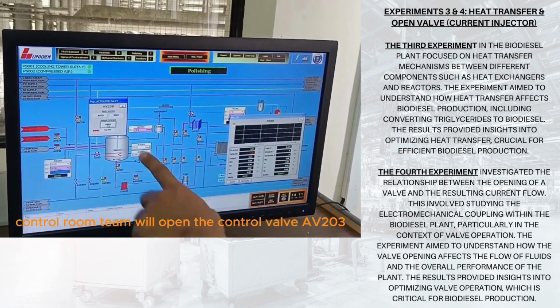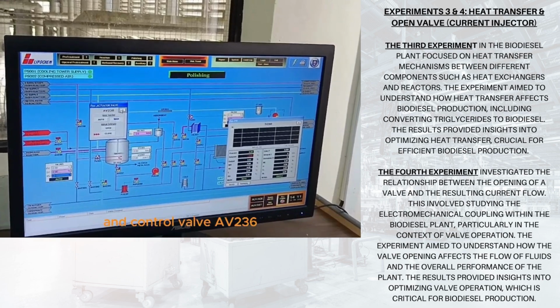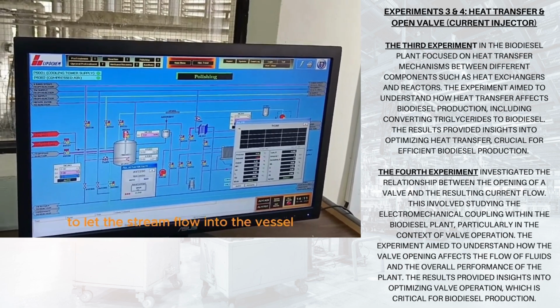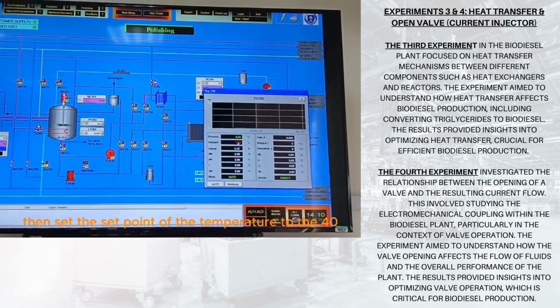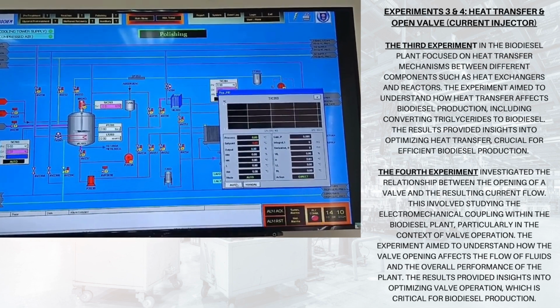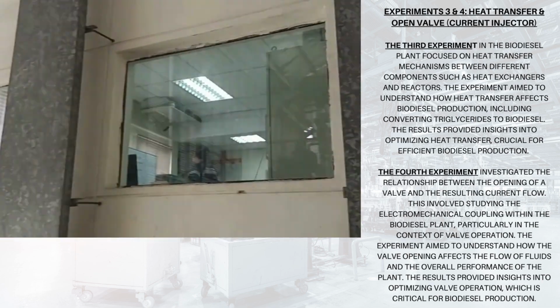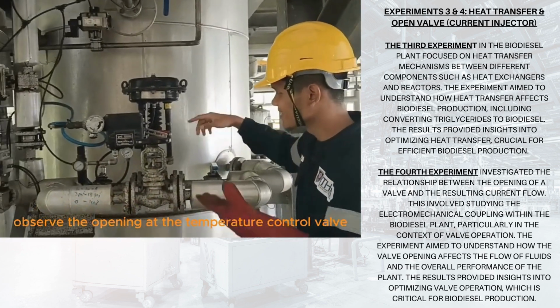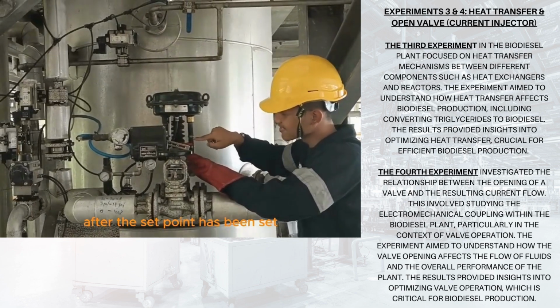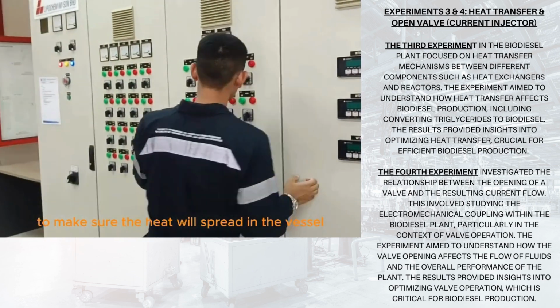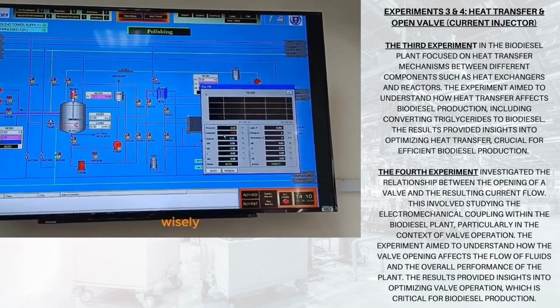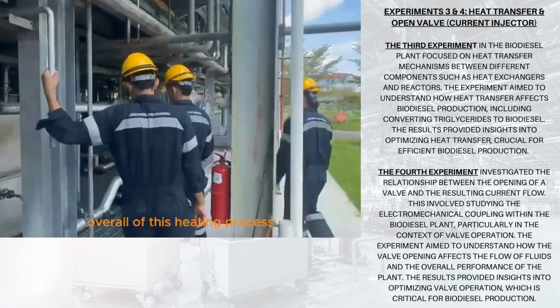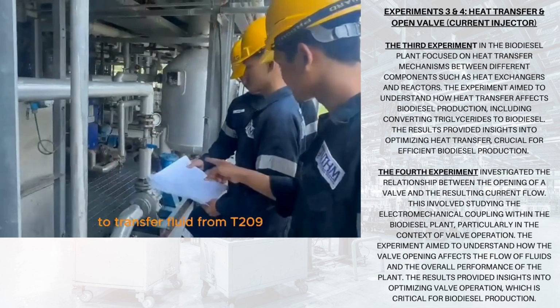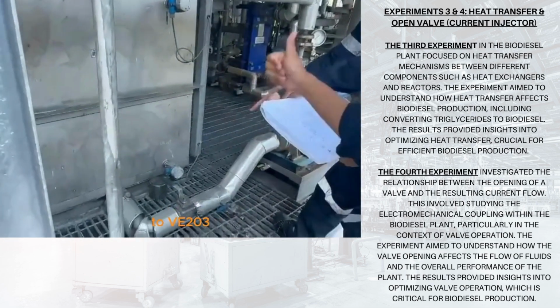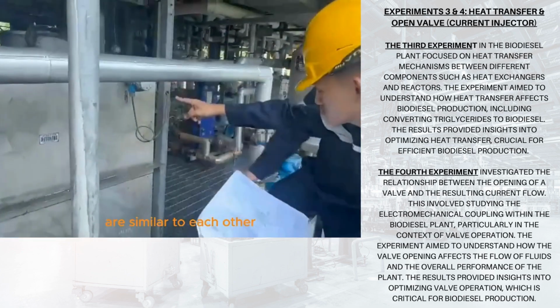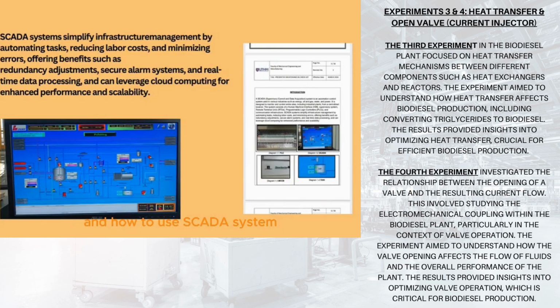After that, the control room team will open control valve TV203 and control valve AV236 using the SCADA system to let the steam flow into the vessel. Then, set the set point of the temperature to 40 degrees Celsius at the TIC 203. The plant team will observe the opening of the temperature control valve after the set point has been set. Then, open the mixer 203 to make sure the heat spreads in the vessel well. Overall, this heating process has the same concept as experiment 2 to transfer fluid from T209 to VE203, where the procedures are similar to each other, by doing line tracing and using the SCADA system.